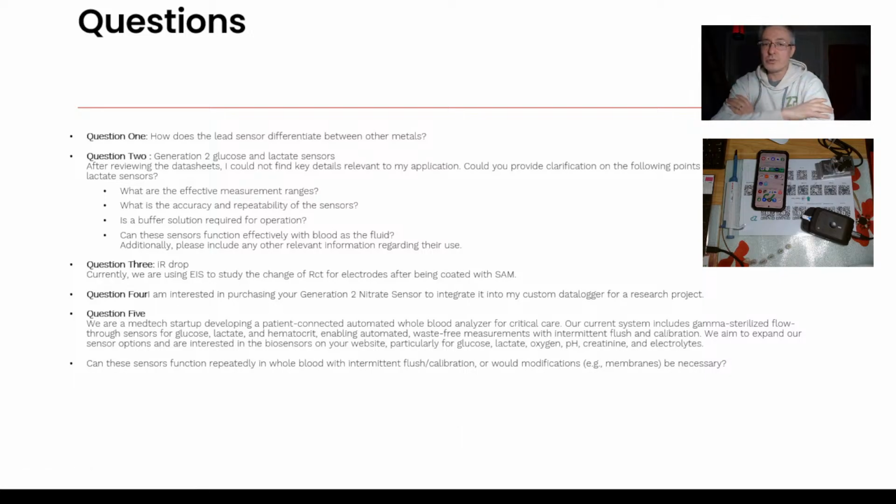Can they be used intermittently? They can. This person has a very robust setup. What I mean by that is they put a sample in, get results, do a wash, do a calibration, then put a sample in, get a result, do a wash, do a calibration. That's really going back to question number 5.